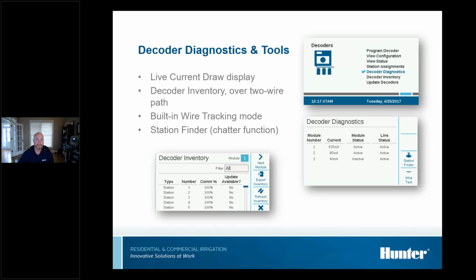Has some great decoder diagnostic tools. You can see a live current display, decoder inventory. This is a great feature. If you've got a really large property, it'll take an inventory of every decoder out there on the system, how well it's communicating back to the controller, and then you can save that to the SD card in the back of the faceplate. The next year when you do your spring startup, you can do another one and compare. You can say, okay, I've got one station that's not responding, let me go check that one out. There's a lot of other diagnostic features we'll dive more into in parts 2 and 3, but that's the gist of what this controller can do.